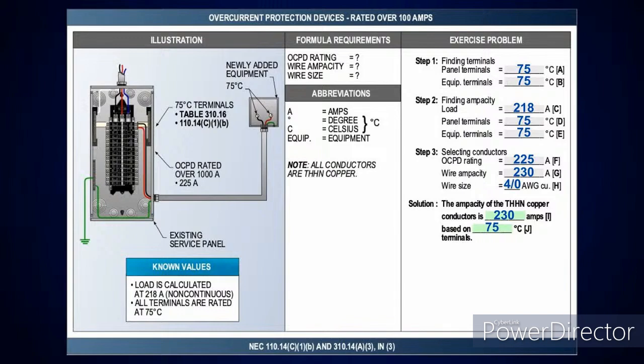Okay, so in this case, I'm in the 75 degrees C column, and I come down and pick up 230 amps as the next size above it. Come across, that's going to tell you it's a 4/0 conductor. Now, I have two options for that. I could protect the load, which would be a 225 amp overcurrent device, or I could protect the conductor, which would be a 250 amp overcurrent device. Okay? Right. But they're going to have you do the minimum, so it's going to be a 225.